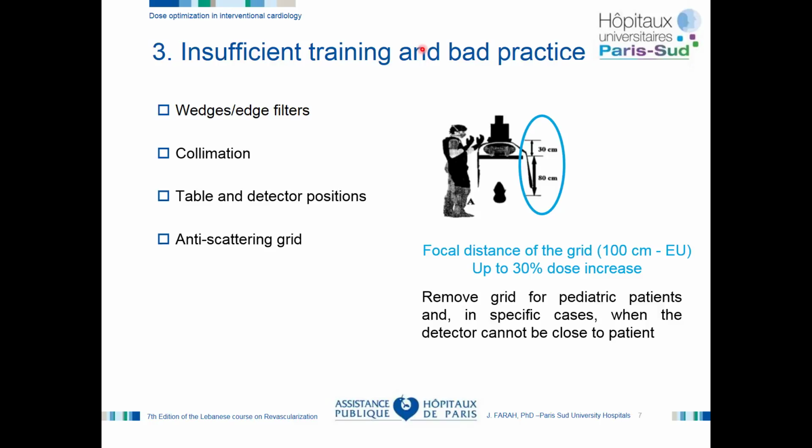If I may give a specific recommendation, I would say definitely remove the grid if you can't put the detector as close as possible to the patient. It's far better for the radiation protection and also for the image quality. And for pediatrics, definitely remove the grid.